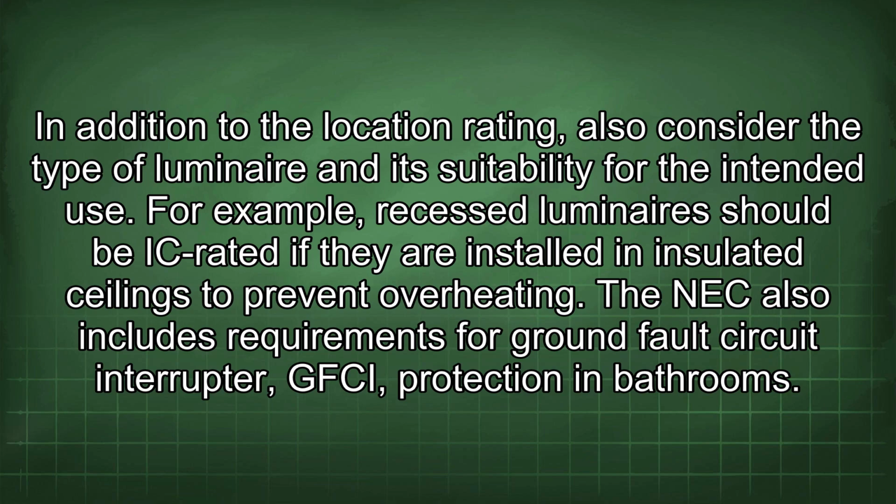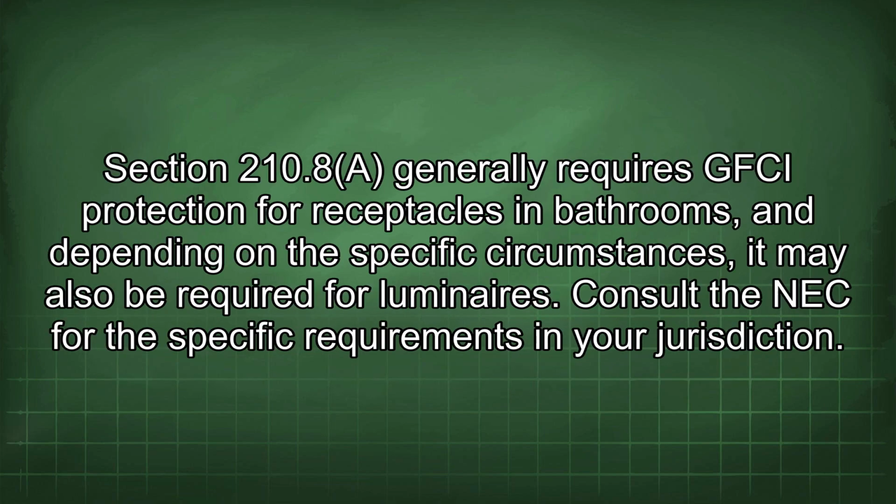In addition to the location rating, also consider the type of luminaire and its suitability for the intended use. For example, recessed luminaires should be IC rated if they are installed in insulated ceilings to prevent overheating. The NEC also includes requirements for ground fault circuit interrupter (GFCI) protection in bathrooms. Section 210.8 generally requires GFCI protection for receptacles in bathrooms, and depending on the specific circumstances, it may also be required for luminaires. Consult the NEC for the specific requirements in your jurisdiction.